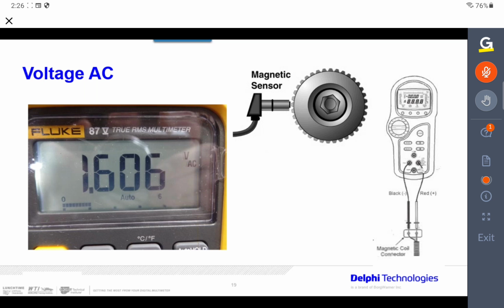The main reason is I get a more accurate reading instead of just plugging one side or the other. I want to make sure I get the proper AC reading when I'm doing my testing on it. And you need to be above about 30 RPM before you actually get a stable reading.